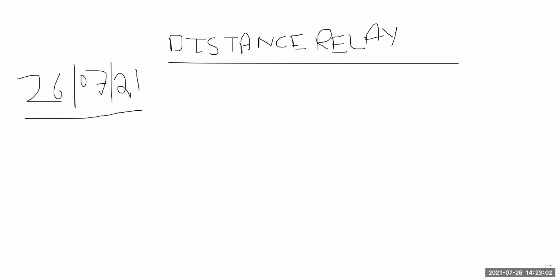The distance is calculated from the generating unit. Based on the distance, the impedance is calculated by relating the fault voltage and the fault current. So if one asks you what is a distance relay, then this is how you could answer it.